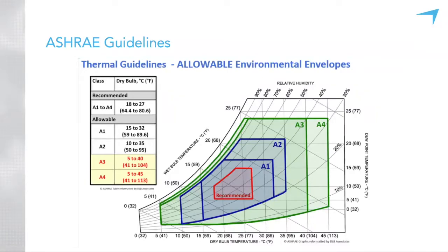When we measure temperatures within the data center at the rack level, ASHRAE recommends as a bare minimum temperature sensors at the end of each row: at the bottom, middle, and top of the rack. Additionally, as a minimum, one rack in the middle of that row should be fully instrumented.